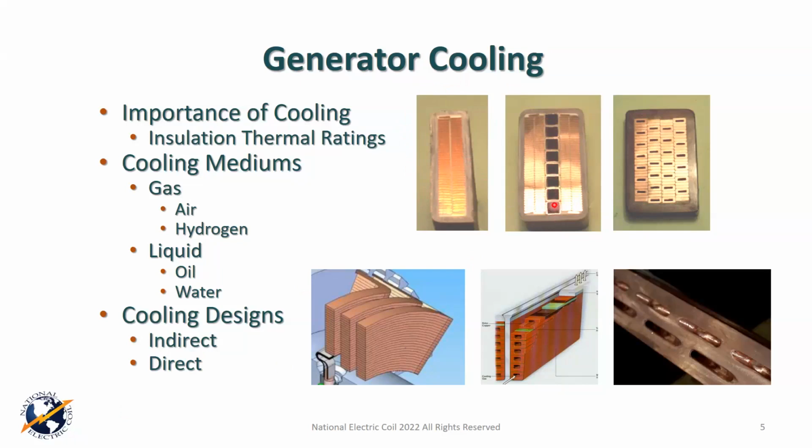And if any of you have a 501 D5 D5A generator, it's also called a Westac. That's one of the very unusual ones. It has an inner or direct cooled air machine. It's very unusual. And the tubes are much bigger than the tubes you see in this picture. And you may be saying, well, why? Well, it's pretty simple. You need a lot more air than you do hydrogen. In fact, it's about 3 times the size overall. Okay, so the air is not as efficient, so you need more of it, and that's why that's done.